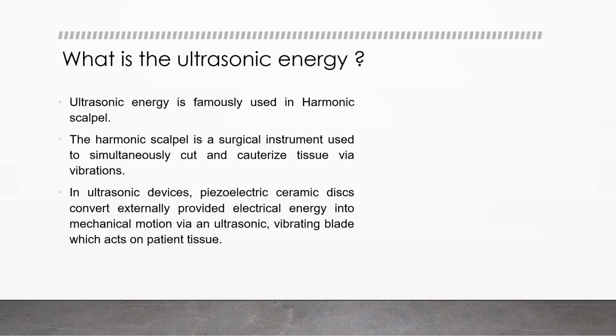So what is ultrasonic energy? Ultrasonic energy is famously used in the harmonic scalpel. The harmonic scalpel is a surgical instrument used to simultaneously cut and cauterize tissue via vibration. In an ultrasonic device, a piezoelectric ceramic disc converts the externally provided electrical energy into mechanical motion via an ultrasonic vibrating blade which acts on the patient's tissue.